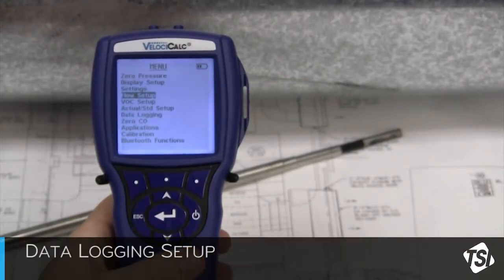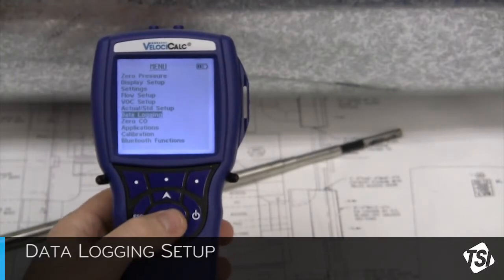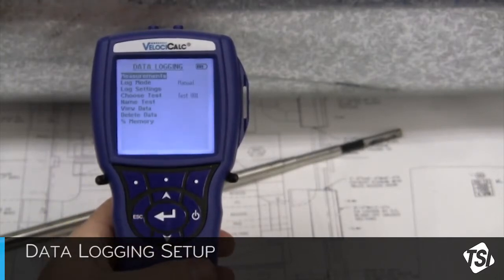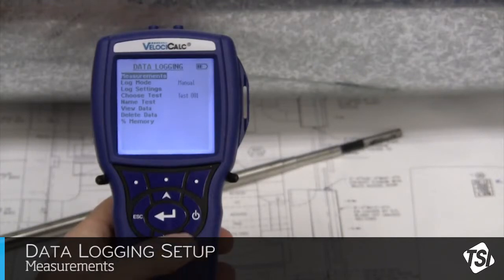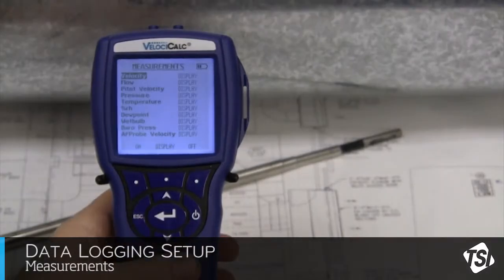Since we'll be making use of the data logging feature to take this airflow measurement, we will need to verify we are using the correct data logging settings. From the main menu screen, scroll down to Data Logging and press the Enter button to open the data logging menu. First, we want to make sure the appropriate measurements are being logged. With measurements highlighted, click on the Enter button. If the unit is set to display, it means that if the measurement is displayed on the main screen, then that measurement will be logged. This is the default setting.